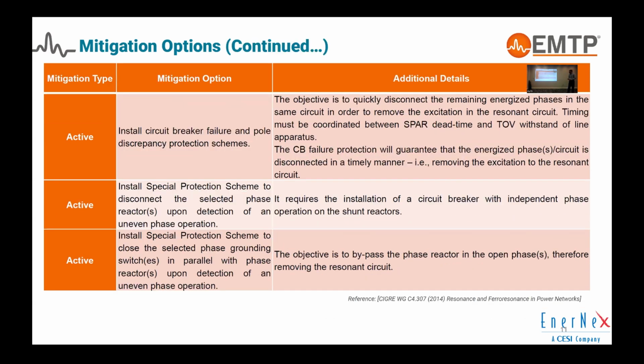And among the active options, these are basically special protection schemes. For example, if an unbalanced operation of the breaker is detected, you take out another breaker, or you bypass the shunt reactor, or you disconnect the shunt reactor on a particular phase.